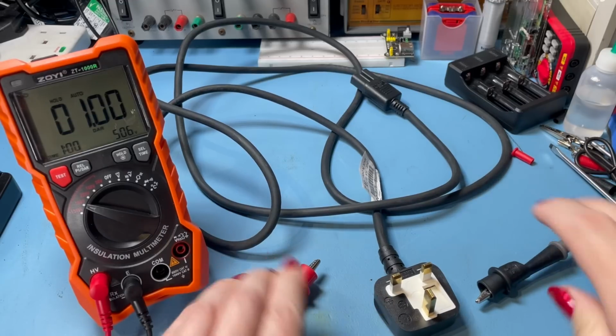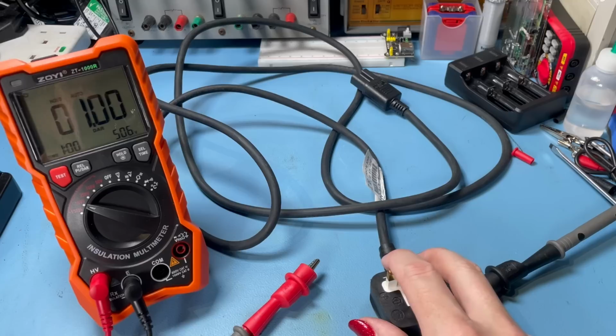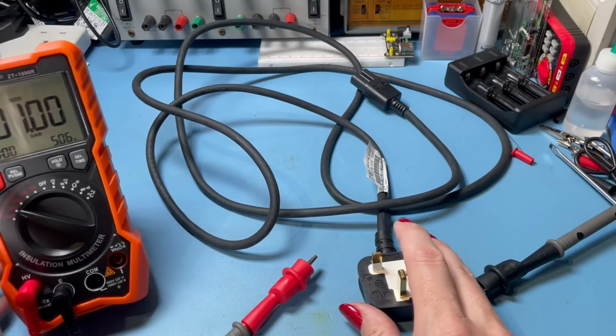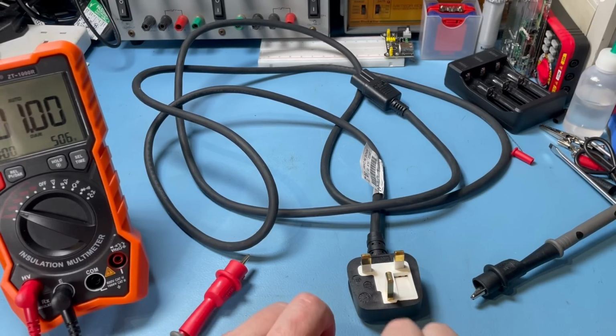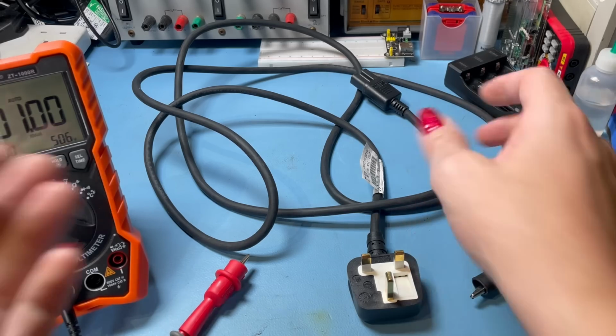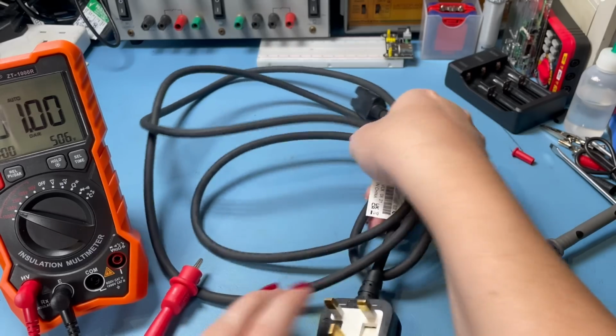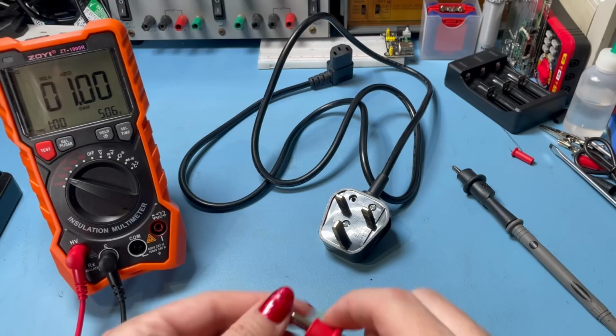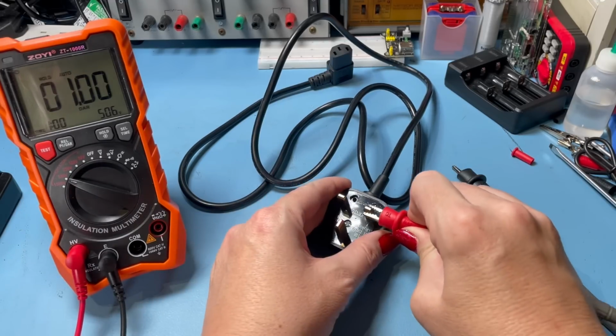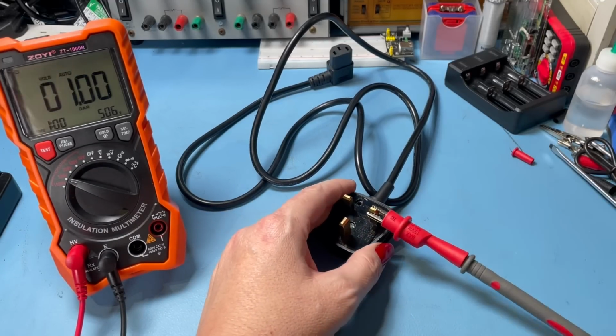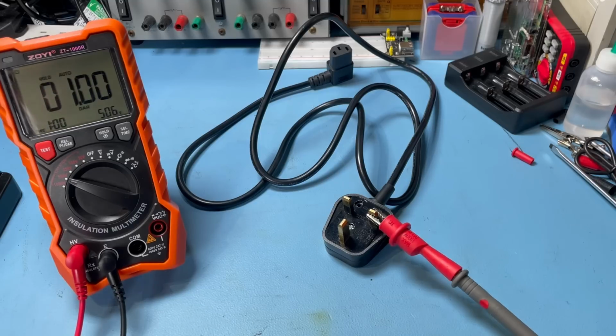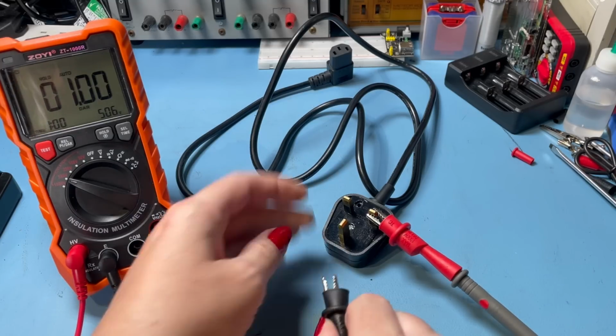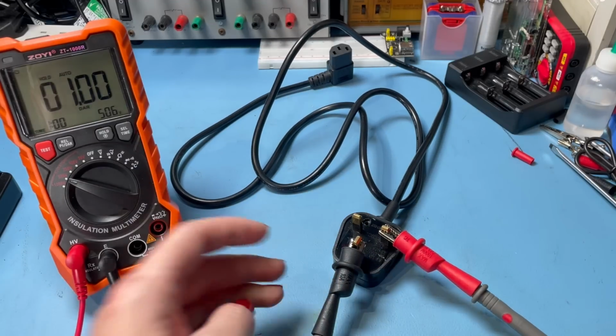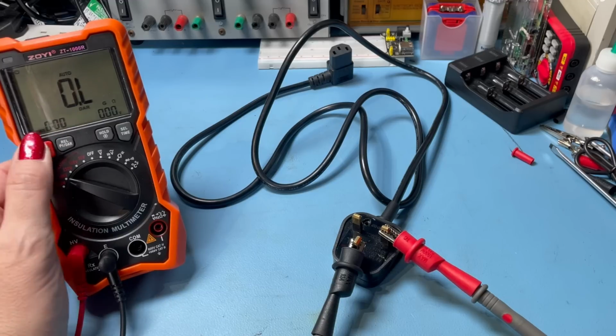Now, as I say, not an expert on DAR, but I would suggest that this cable tests fine. I'm getting the same readings on all three pins, and again this passed when I checked it with my PAT tester, so I'm going to go ahead and say this cable is fine. So let's go ahead and test this other kettle lead, which has a PVC insulation on it, and we can note the differences from that to the one with the rubber insulation, which is best. Live to earth, 500 volts, DAR, go.